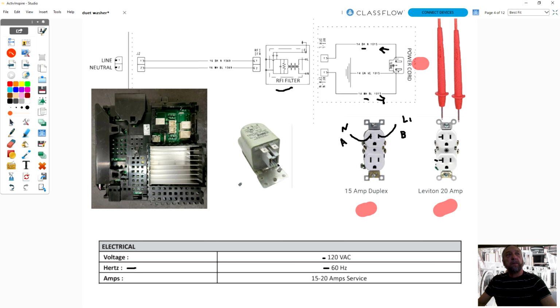Two of these terminals are power coming in and two are power going out. So we've got 120 coming in here, marked line 1 and neutral. On the other side, power comes out and goes to the board, to J2 on the board. I'll bring that up on the next screen.